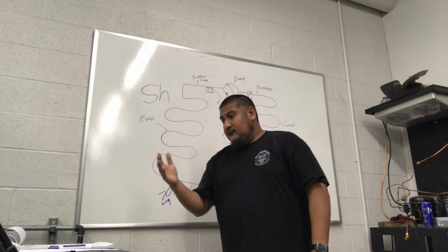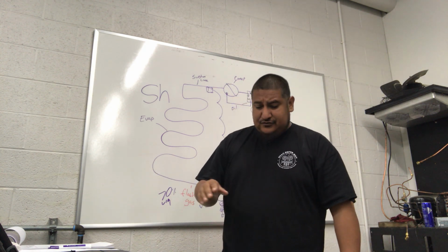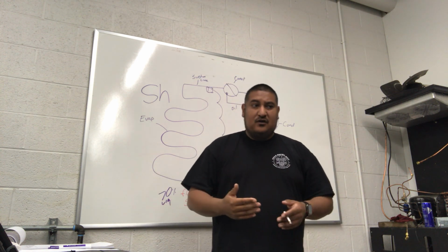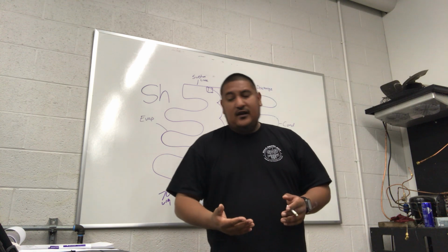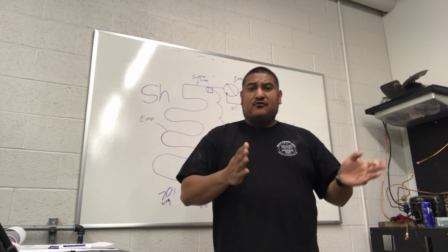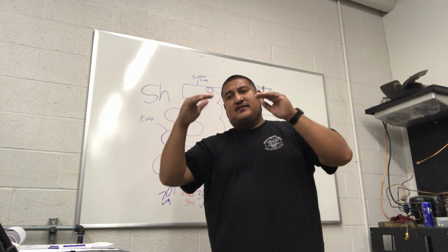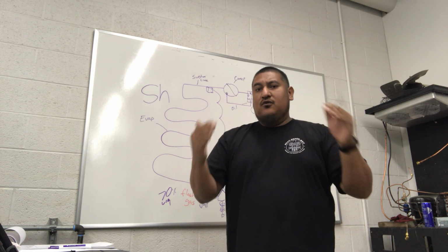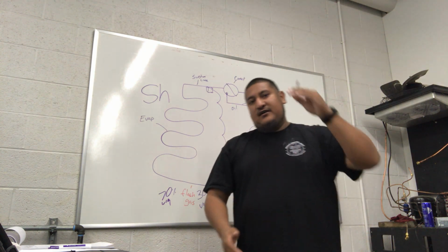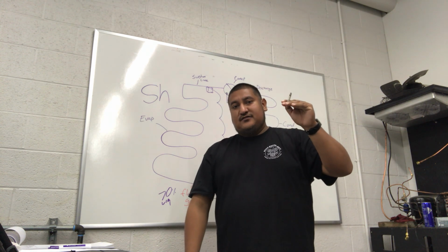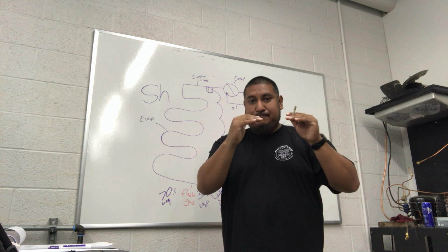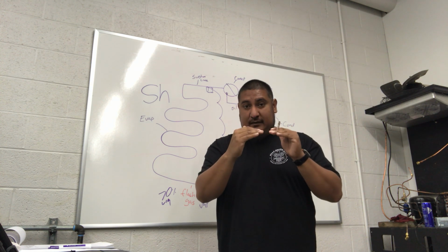Now, when you guys look at these gauges, those numbers won't change, right? You have what's called a PT chart, which is a pressure temperature chart, right? Every refrigerant is going to have a temperature that goes with that pressure. It won't change. You can look at any PT chart and it'll tell you, hey, at 100 pounds of pressure, you're going to have 60 degrees of refrigerant temperature. That's its saturation temperature, right?